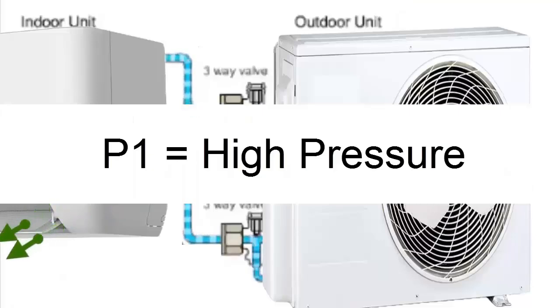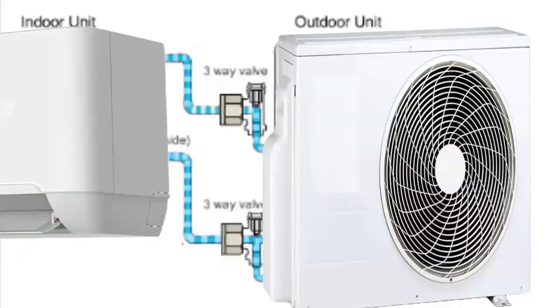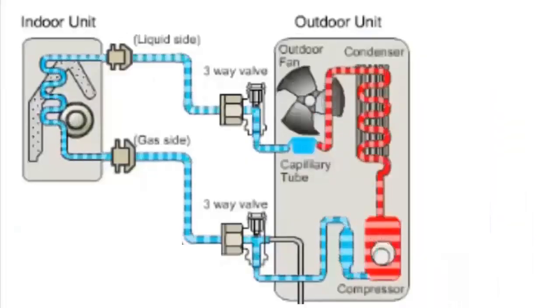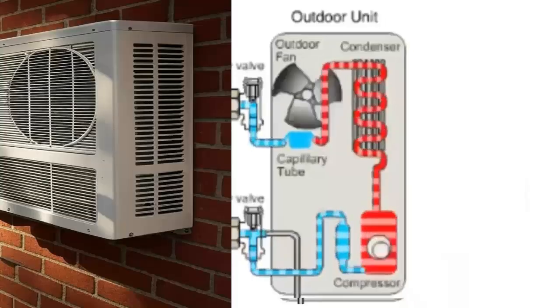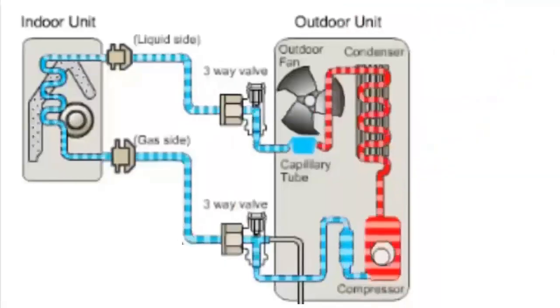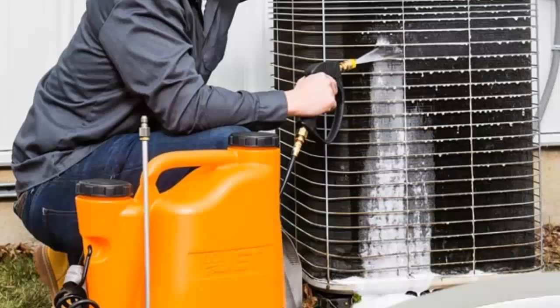However, for HRDN series outdoor unit models, Code P1 indicates protection from high pressure. Recommendations: A. Check that the outdoor unit fans are working correctly, and verify the capacitor if the fan uses one. B. Verify the cleanliness of the outdoor unit's coil.